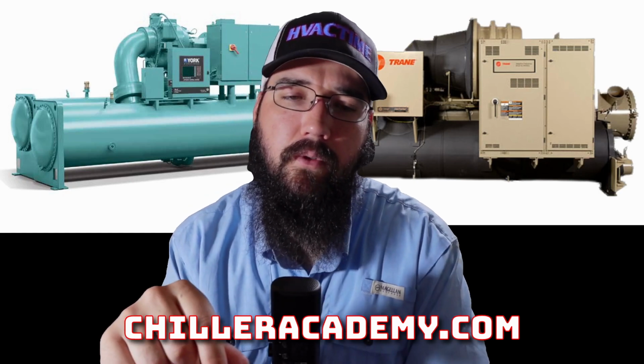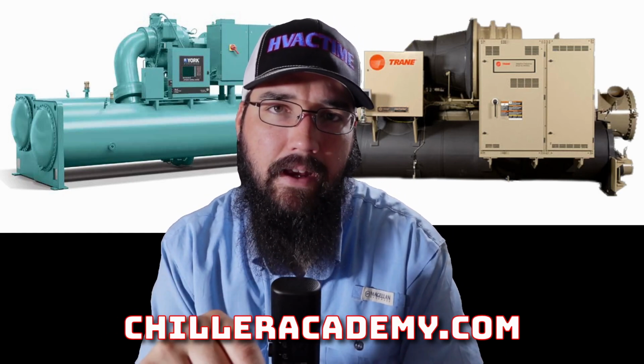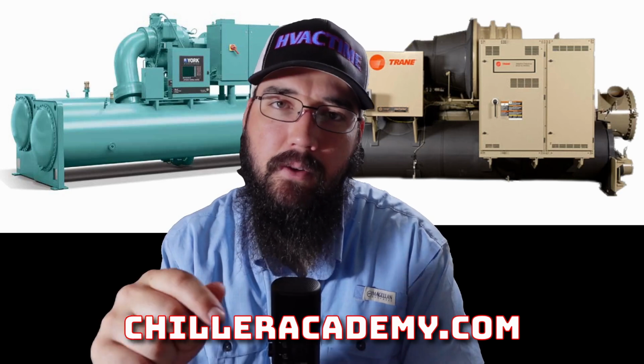Now, one of the things that low pressures have that high pressures don't need is a purge system. Because it's low pressure and it operates in a vacuum, there's a lot of risk of pulling in non-condensables. That's just a known thing in this industry that we deal with. That's why we have purge systems. It is really important to mitigate and manage the purge system needing to function at all, more than anything else.